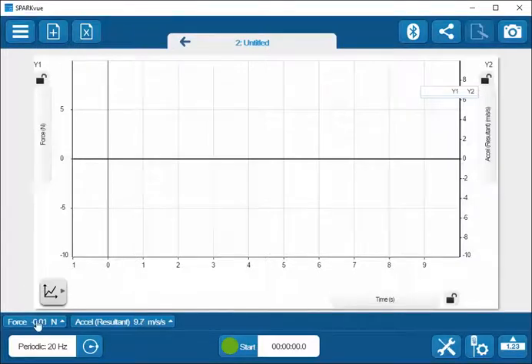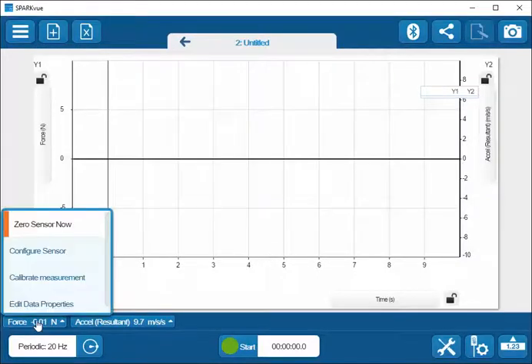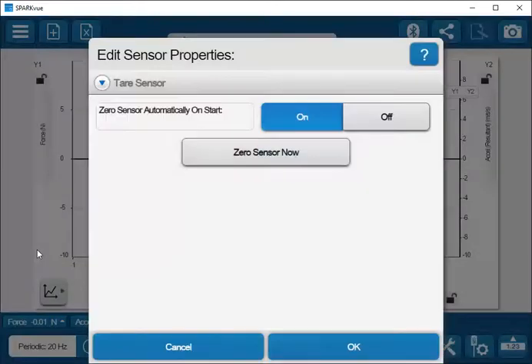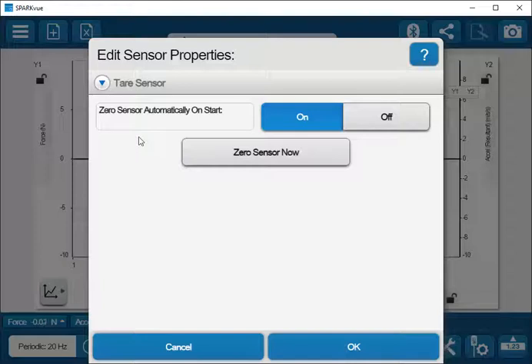To access the other items from this menu, I can click again on the Live Data. I can click on Configure Sensor. Once I've done that, I'm presented with the ability to zero the sensor automatically on start or again to zero the sensor now.